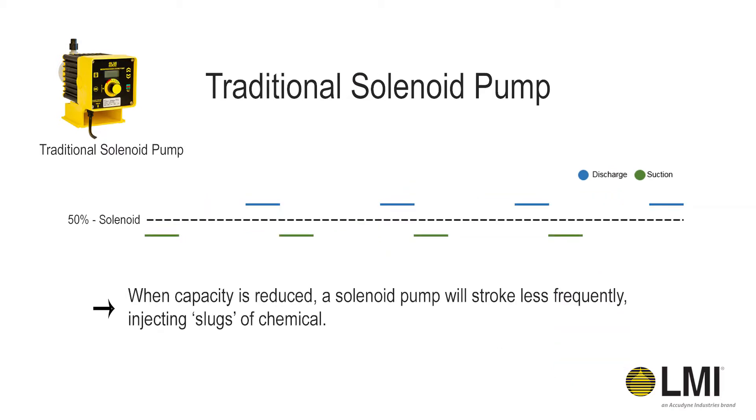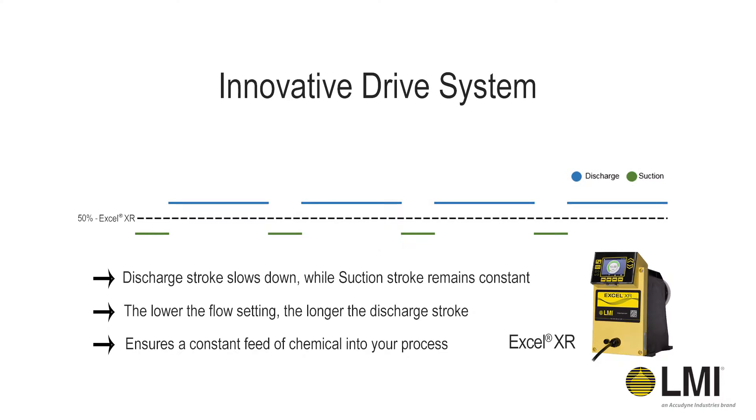On a solenoid pump, as you turn down the capacity, the pump strokes less frequently, so it's pushing a full stroke of chemical into the system quickly at less frequent intervals as capacity is turned down. As the Excel XR's capacity is turned down, the discharge stroke slows down, while the suction stroke remains constant — ensuring a constant feed of chemical into your process.